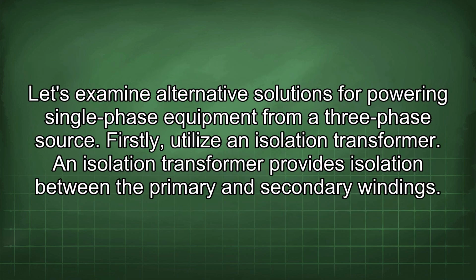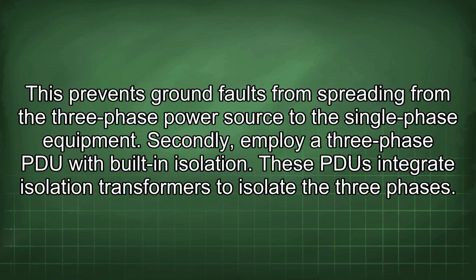Let's examine alternative solutions for powering single-phase equipment from a three-phase source. Firstly, utilize an isolation transformer. An isolation transformer provides isolation between the primary and secondary windings. This prevents ground faults from spreading from the three-phase power source to the single-phase equipment. Secondly, employ a three-phase PDU with built-in isolation. These PDU integrate isolation transformers to isolate the three phases.